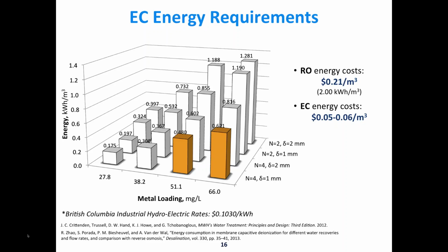When comparing it to an incumbent water treatment technology like reverse osmosis, it's about a quarter of the price. And when compared to traditional chemical coagulation, from what we've found, electrocoagulation is a little bit more expensive, but a lot of these studies don't take into account transportation cost of chemicals. As we know, we're looking at electrocoagulation as a potential alternative treatment technology for remote communities. So if we were to consider the transportation of these chemical coagulants to a remote community, I think we would see the energy cost for both electrocoagulation and chemical coagulation to be very comparable.